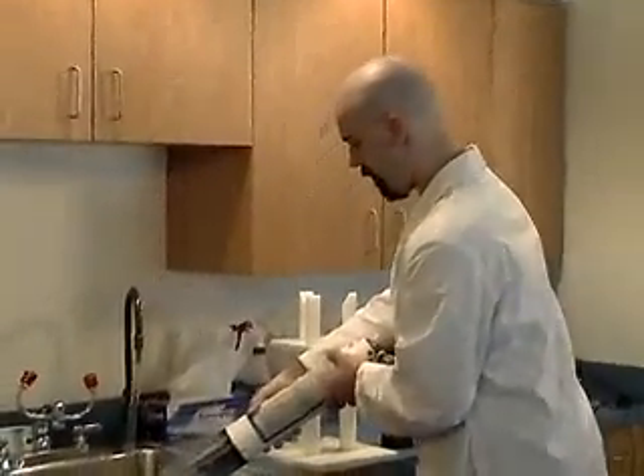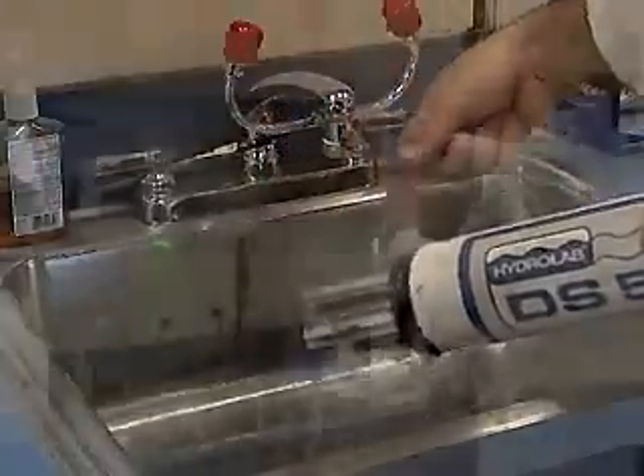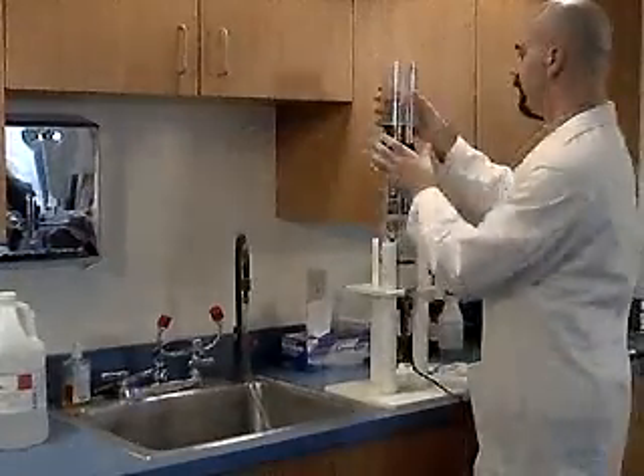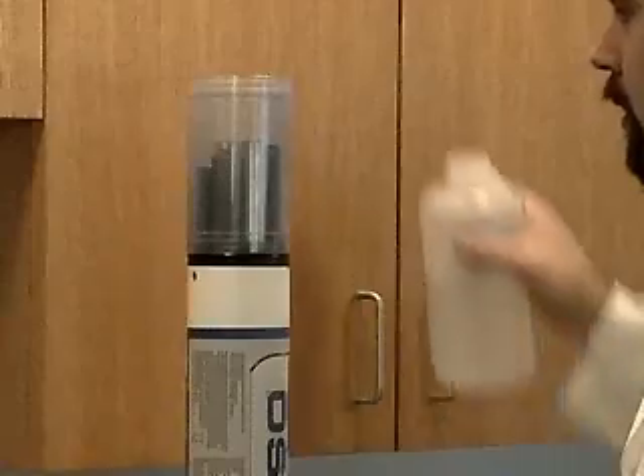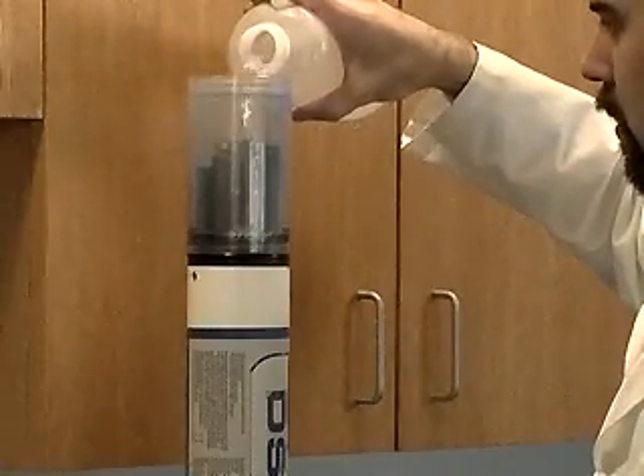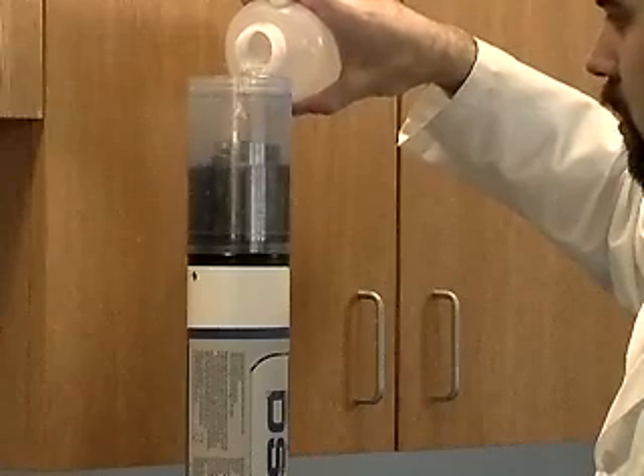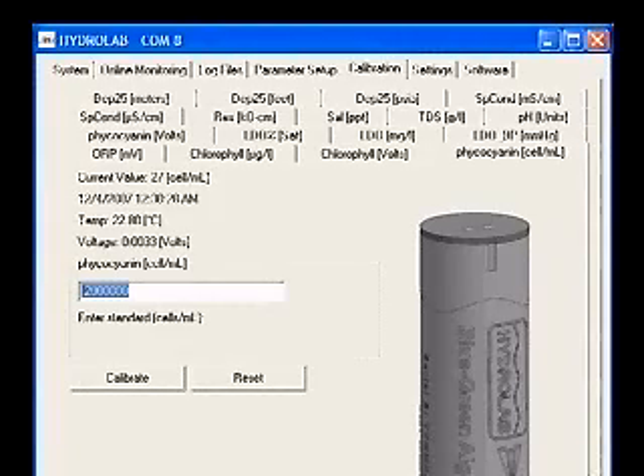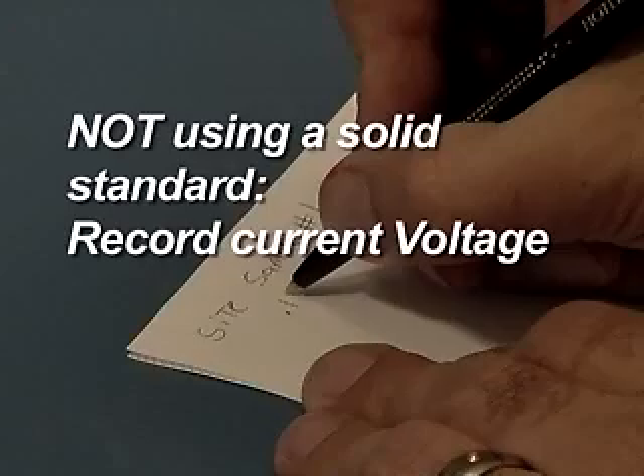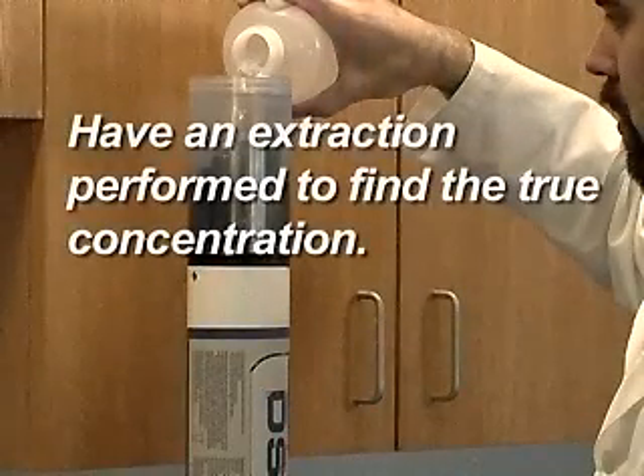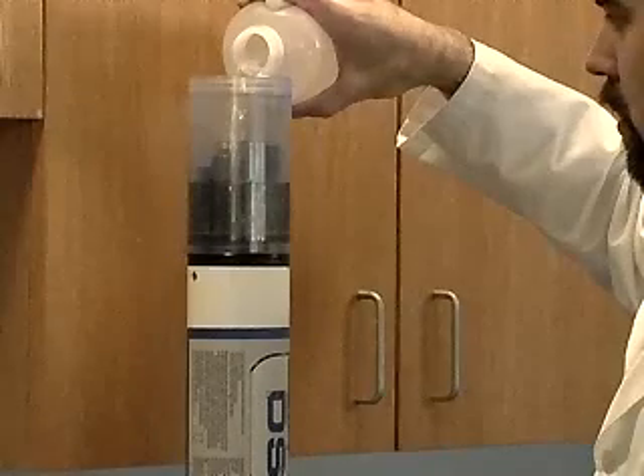Empty the storage cup and rinse the sensors. Dry the sensors and attach the storage cup. Fill the cup to the threads with a fresh sample from the deployment site. Wait 1 minute for the readings to stabilize. Record the voltage reading. Have an extraction performed on the sample to find the true concentration. When the results of the extraction are known, the chlorophyll A sensor is recalibrated using this value.